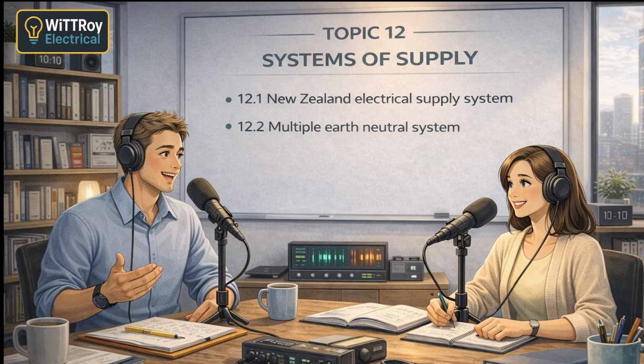Okay, that makes sense. As power gets closer to towns and cities, substations step it back down again. Subtransmission is usually 33 kilovolts, and local distribution is 11 kilovolts. So 11 kV shows up twice, generation and distribution. Good spotting. That catches a lot of people out in exams. Then finally, pole-mounted or ground-mounted transformers step it down to customer supply. That's the 400 and 230 volts, yeah? Correct. 400 volts phase to phase for three-phase and 230 volts phase to neutral for single-phase.